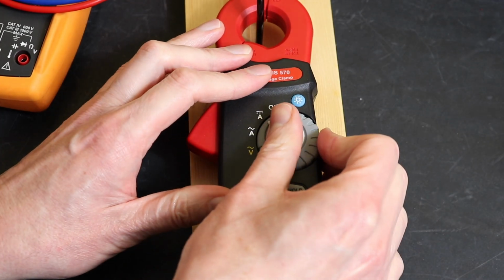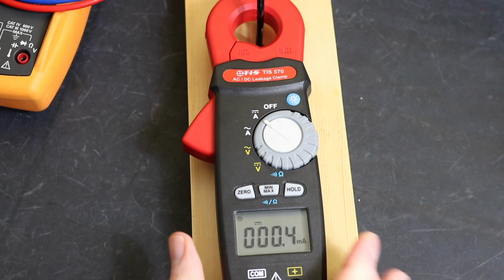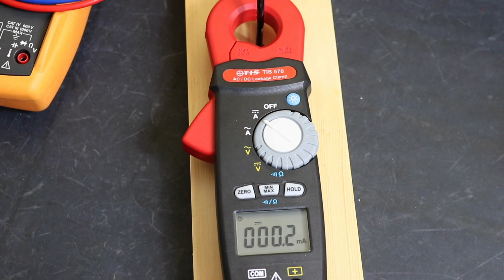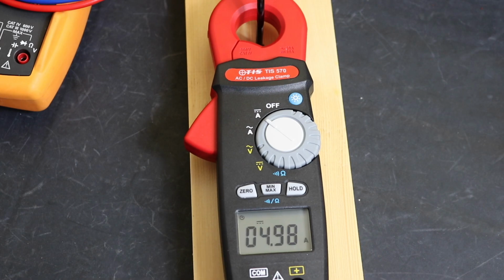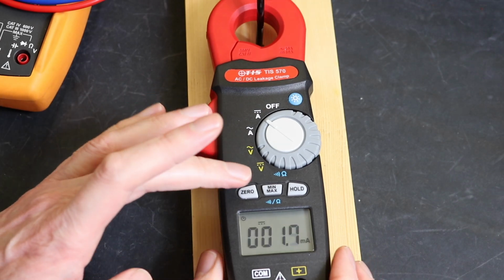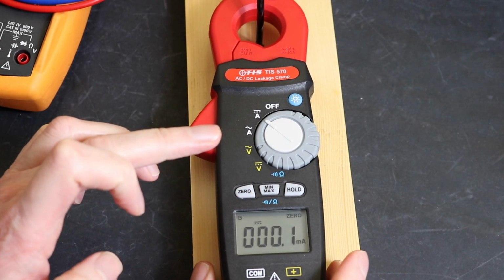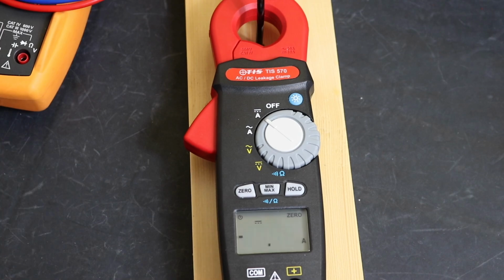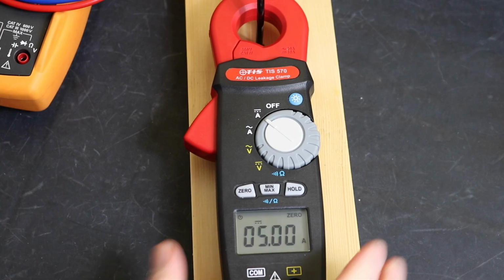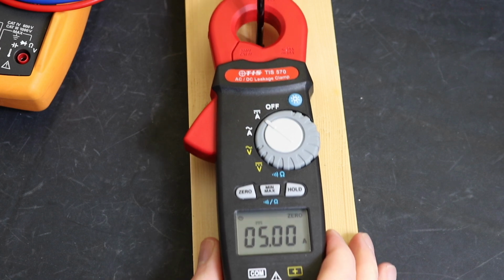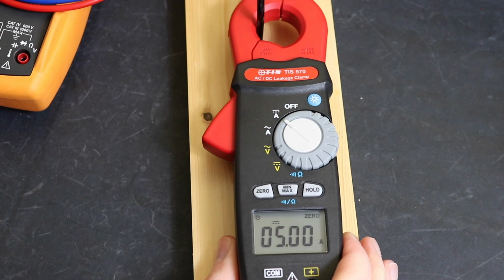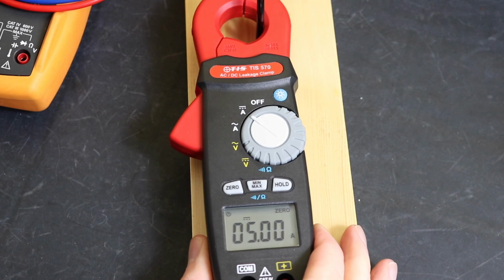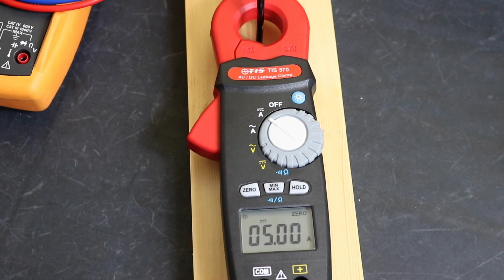To flip him over to there. So now we are DC amps. 0.03, we can zero, but we're 0.02, so we will switch back on. So this again is half full scale, 5 amps, and we have 4.98, so a little bit out. And let's just switch him off. We're at 1.7, so we'll zero that, and we'll just switch back on again. And we've got 5 exact, so yeah, you can't complain at that, can you? Nothing wrong with the DC amps measurement there whatsoever.